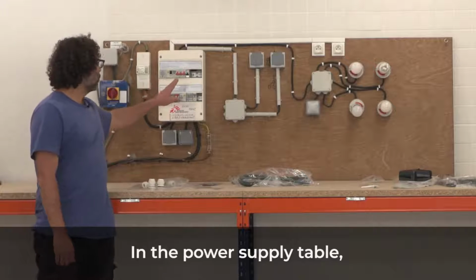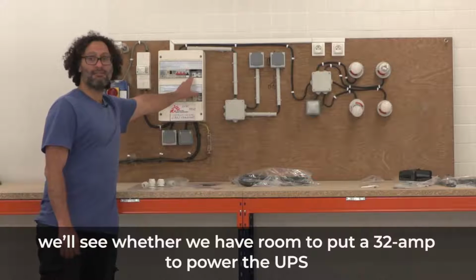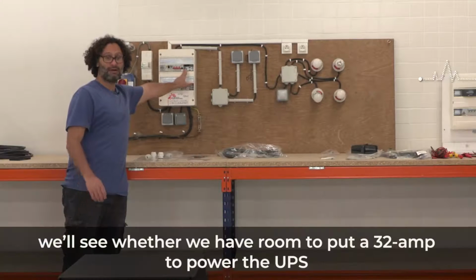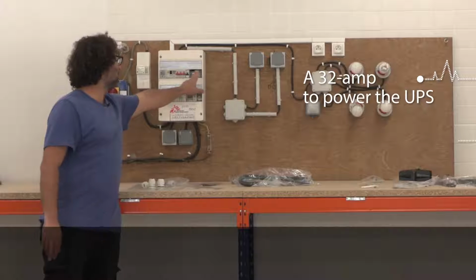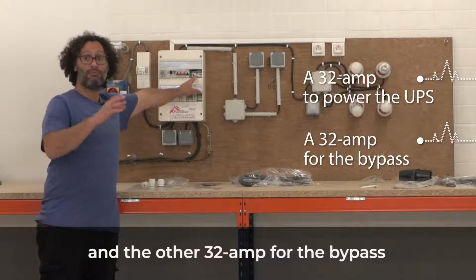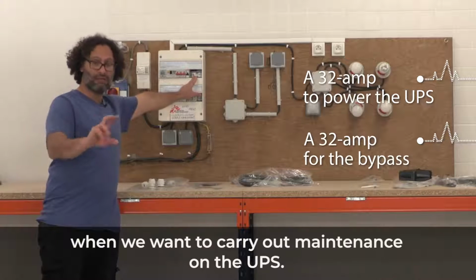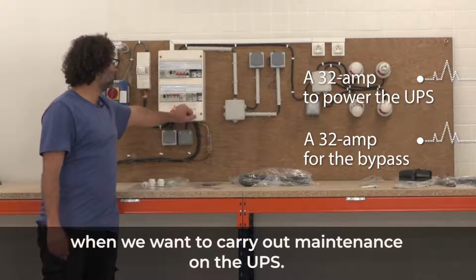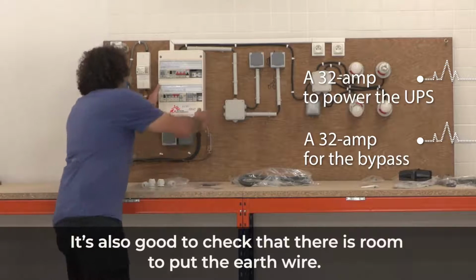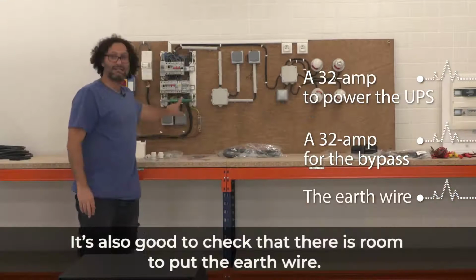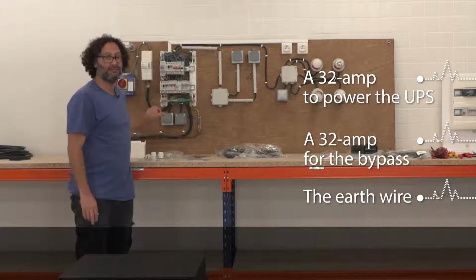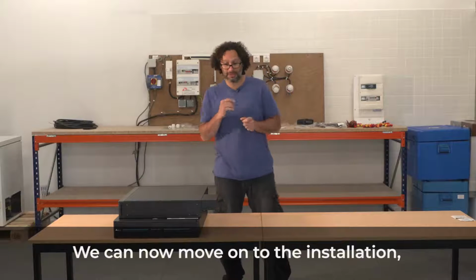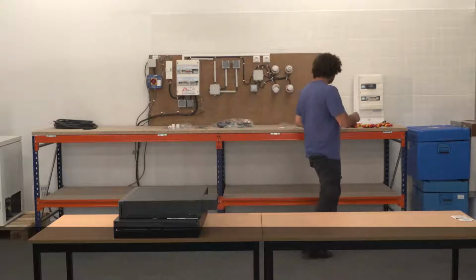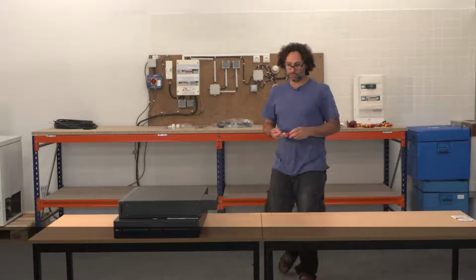In the power supply table, we'll see whether we have room to put a 32 amp to power the UPS and the other 32 amp for the bypass when we want to carry out maintenance on the UPS. It's also good to check that there is room to put the earth wire. We can now move on to the installation, to connecting the UPS.